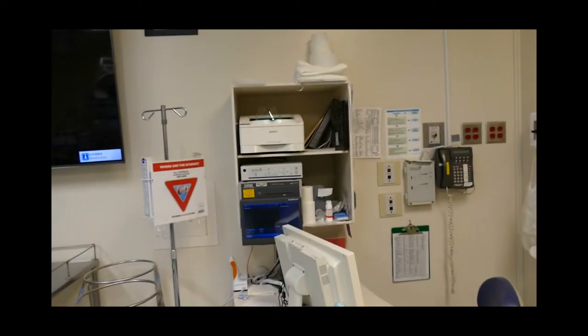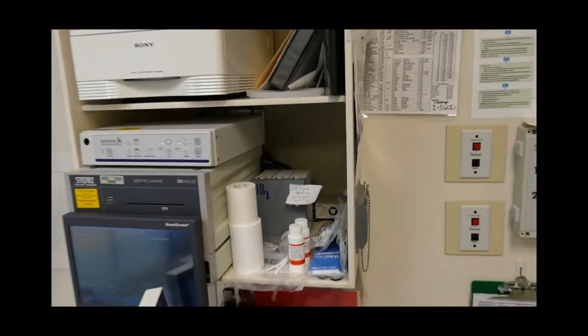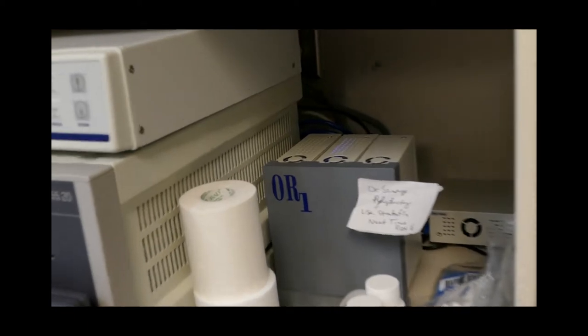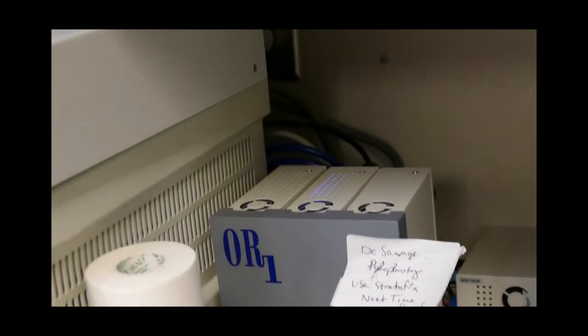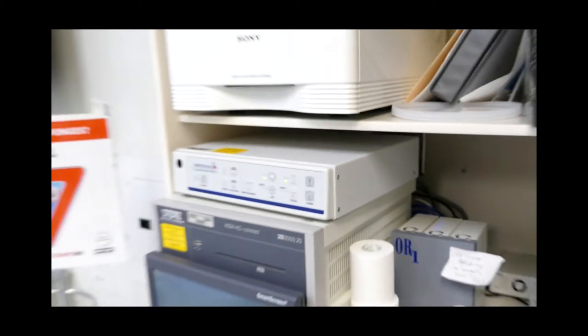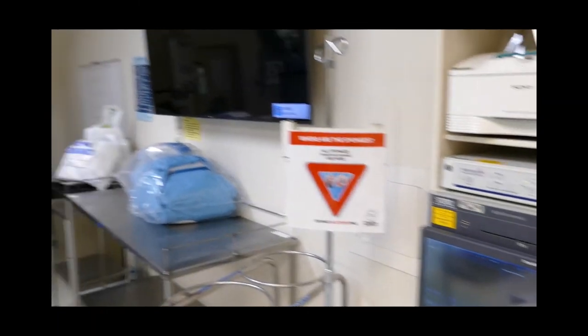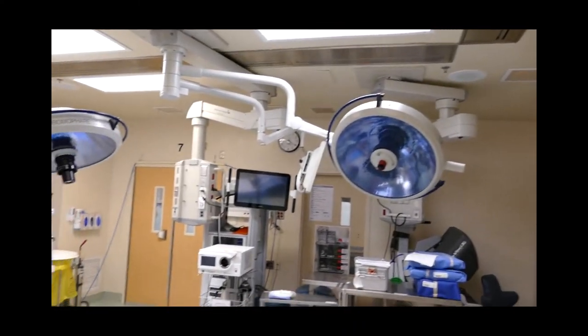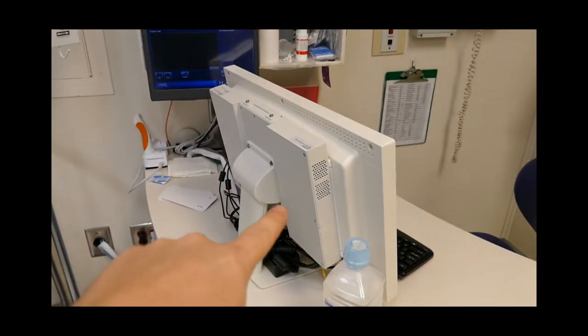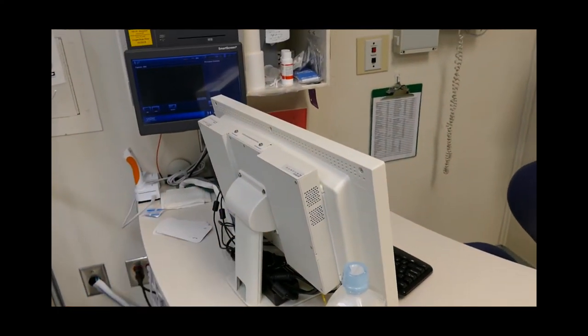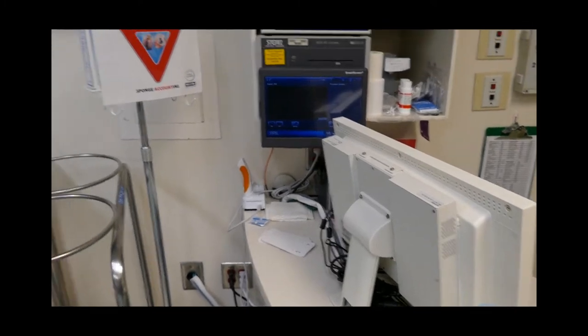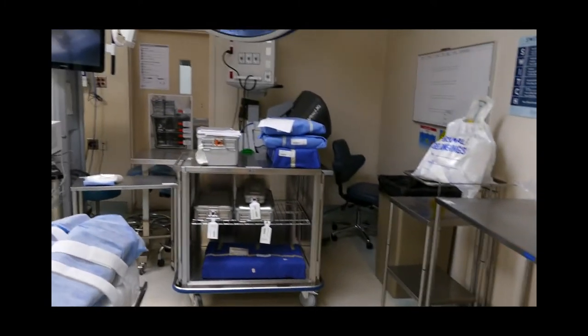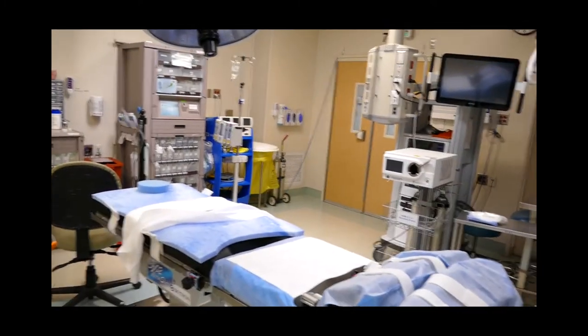So there's that one. I've got more converters over here. Look at this. There are just components all over this Karl Storz system right there. There's that one. I've got them behind every single one of the monitors up here. I've got them behind the shroud right here. So I have little fans everywhere that I'm going to have to go around and clean. And I wasn't expecting that.